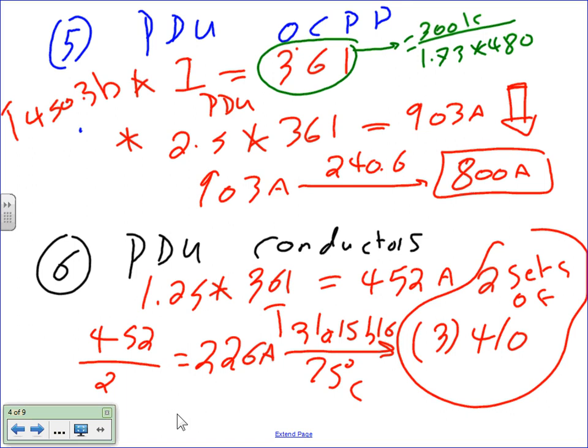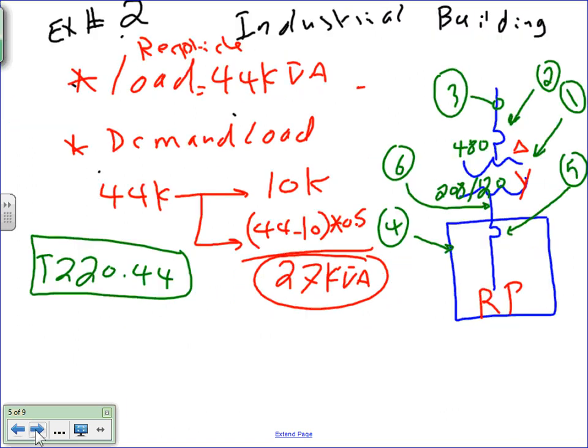The last example that I have for you is panels. Matching a panel. Now this is an industrial building, and I have the following. And I did the calculation. Did I copy all this for you guys? You need to do this tomorrow. First, we're in actually any building. It doesn't have to be industrial. And I have a transformer and a panel for the receptacles. The primary is 480. The secondary is 208. I need a feeder from the transformer to the 208 receptacle panel. And I need a feeder to feed the transformer, overcurrent protection device for the transformer, and so forth.